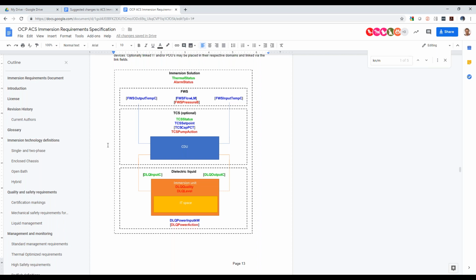Hang on, before you go there, Nigel, let me explain that these values are provided by the immersion technology provider. In our case, that's the connection point on our technology that interfaces with the facility water circuit - it's not part of the facility itself to monitor, it's part of the total immersion solution already. But it might also in some cases extend beyond the cooling provider's domain - for example, if they work with an alternative CDU provider, it may not be possible.